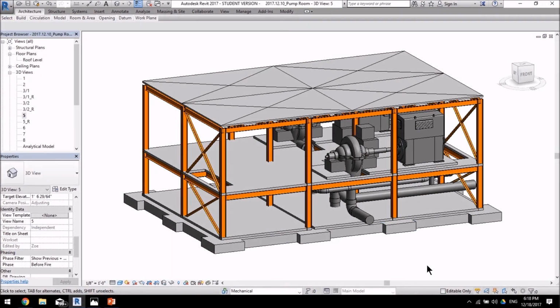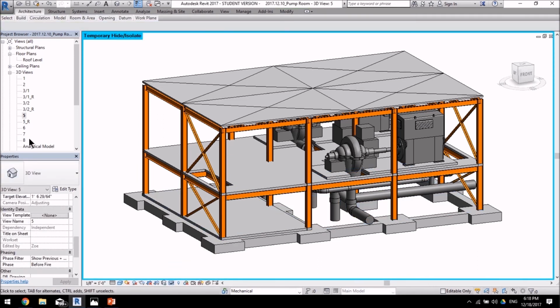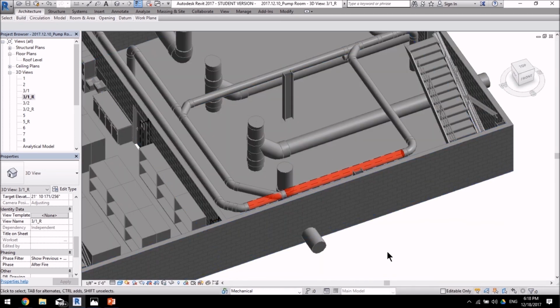When the footing load becomes greater than the allowable soil bearing pressure, as occurring in this case, consequently, we expect footing settlement under columns A and B, leading to the pipe breakage in the pipe room, because, as I mentioned previously, the pipe was tied to the column B. Therefore, according to our analysis, we deduce that the pipe breakage was the indirect consequence of the fire incident inside the storage room.